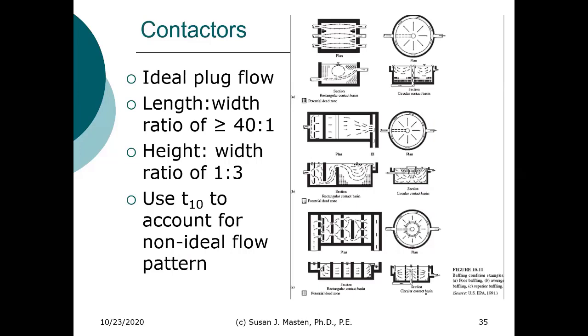With contactors, we want an ideal plug flow and a length-to-width ratio greater than 40 to 1 to help ensure plug flow, especially with our chlorine contactors. Typically a height-to-width ratio of 1 to 3. We'll use the concept of T10 to account for non-ideal flow.